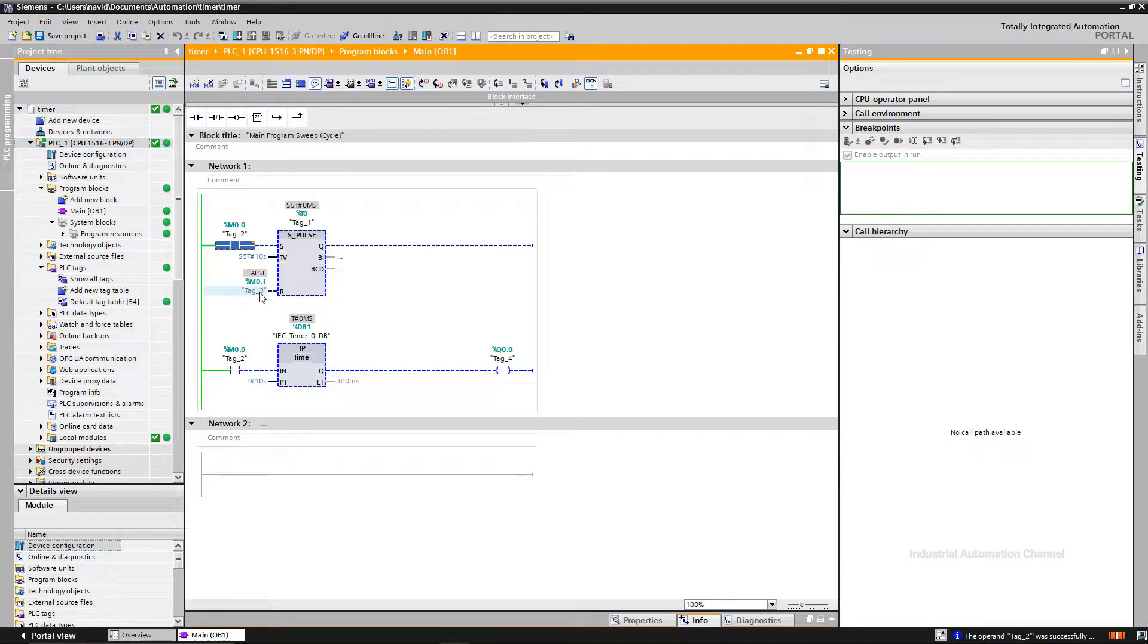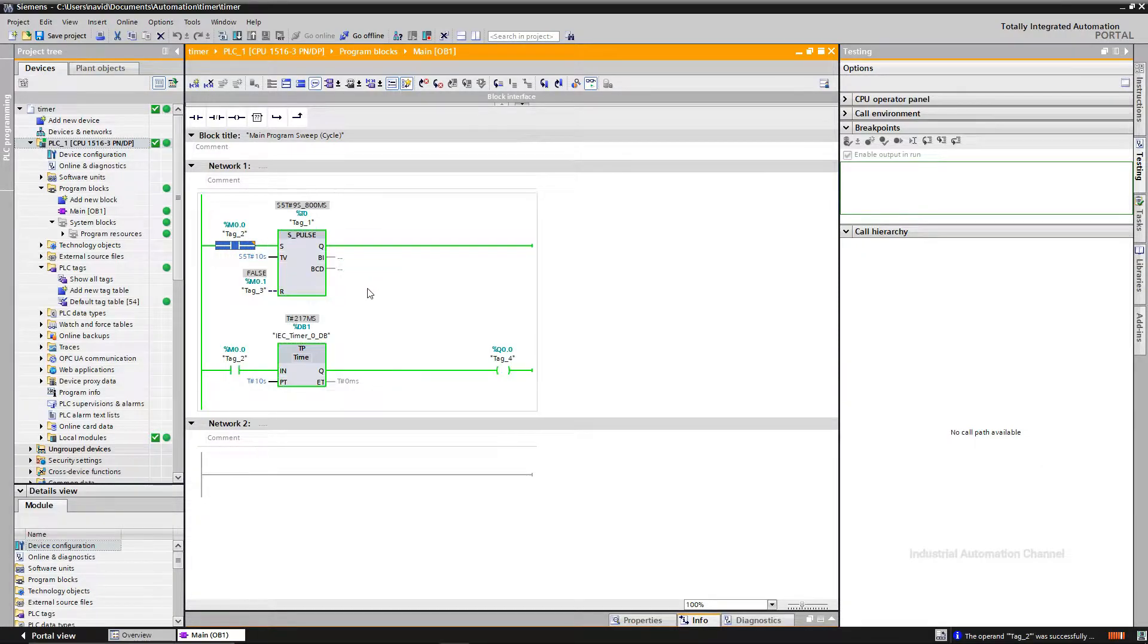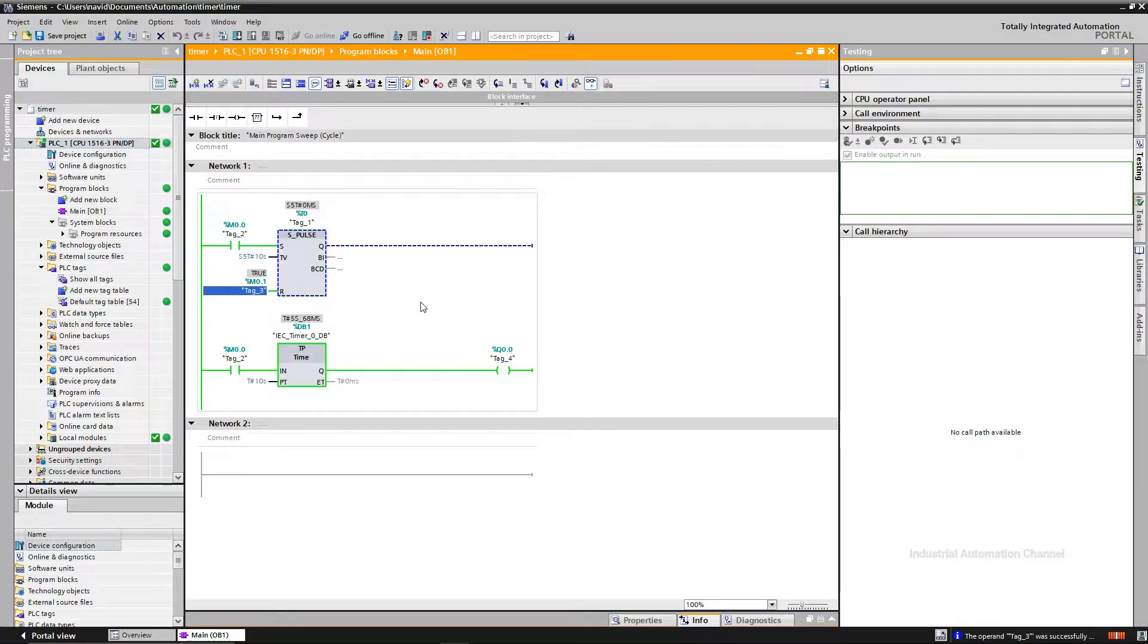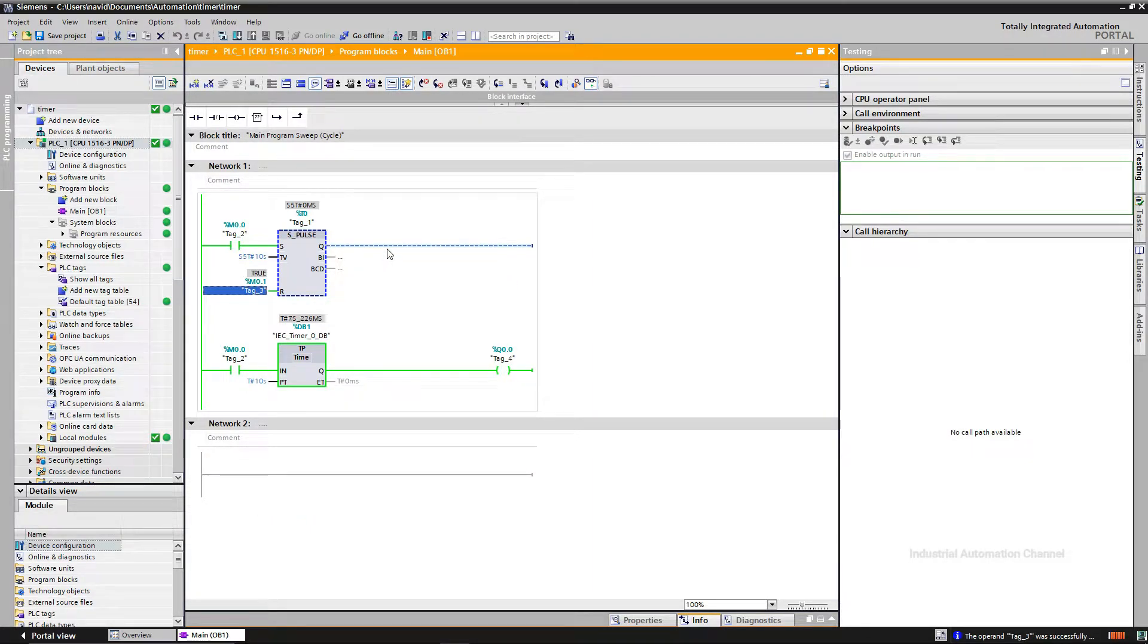S_PULSE has a RESET input. If the timer is running and I press this input, the current value will be set to zero and output Q will be off. As long as the RESET is active, you cannot start the timer.